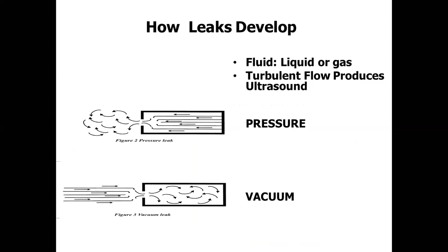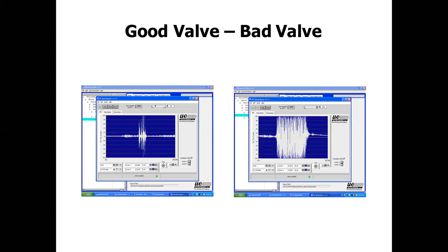Similarly, if there are two walls, one valve in good condition and another in failure or bad condition, then in good condition the ultrasound shows only 2 or 3 spikes in the first figure. But in the second figure there are a number of spikes that indicate that this valve is a failure valve, or it can fail. So that can be measured. Similarly, we can do electrical inspection of switch gear, transformers, insulators, relays, breakers, all using ultrasound. Then bearing inspection is also very effective when the speed is small.